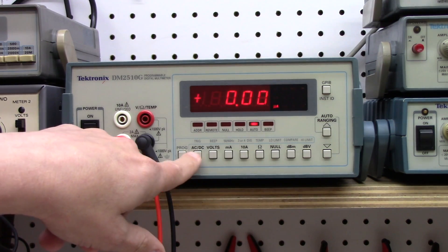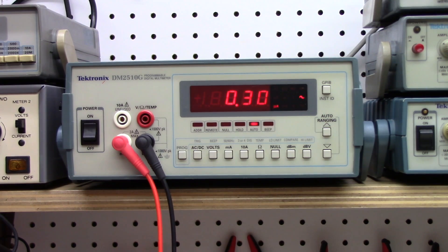Let's go now to AC, and we get our 1 milliamp true RMS signal out, and there it is, bang on, rock solid. I will say that when I first tried this this morning, the current didn't read anything, and that was a little irritating because this had been claimed to have been tested and functioned on every range. Well, you can guess what the issue was. When I pulled it out and looked at it, it looked a little suspicious and measured a huge resistance when I tested it, so when I changed the fuse, it functioned just like it should.